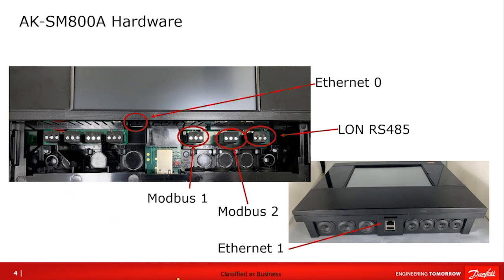This is a depiction of our connection. At the bottom half of the System Manager, if you remove the cover plate, these are the plugs you would see behind that cover. Ethernet zero, highlighted at the top, is our connection point for remote access and for that data extraction on the upstream side. This would just be a standard Ethernet cable. That connection is recessed, so it can be a little hard to recognize initially, but that's our connection point for remote access for the System Manager.